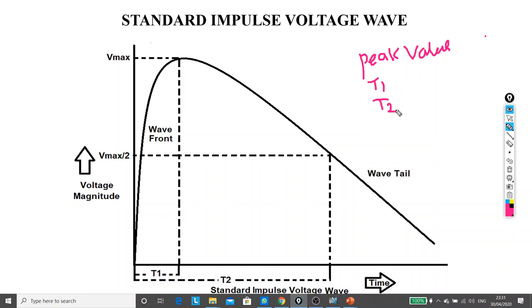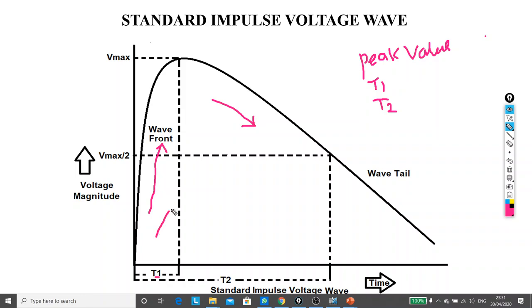The rising portion of the impulse voltage wave is called the wave front, and the falling portion is called the wave tail. The time required by the wave to reach the peak value is denoted as rise time T1, and the time from zero to peak and from peak to half of the peak value on the wave tail is denoted as T2, which is called the time to decay to half of the peak value.